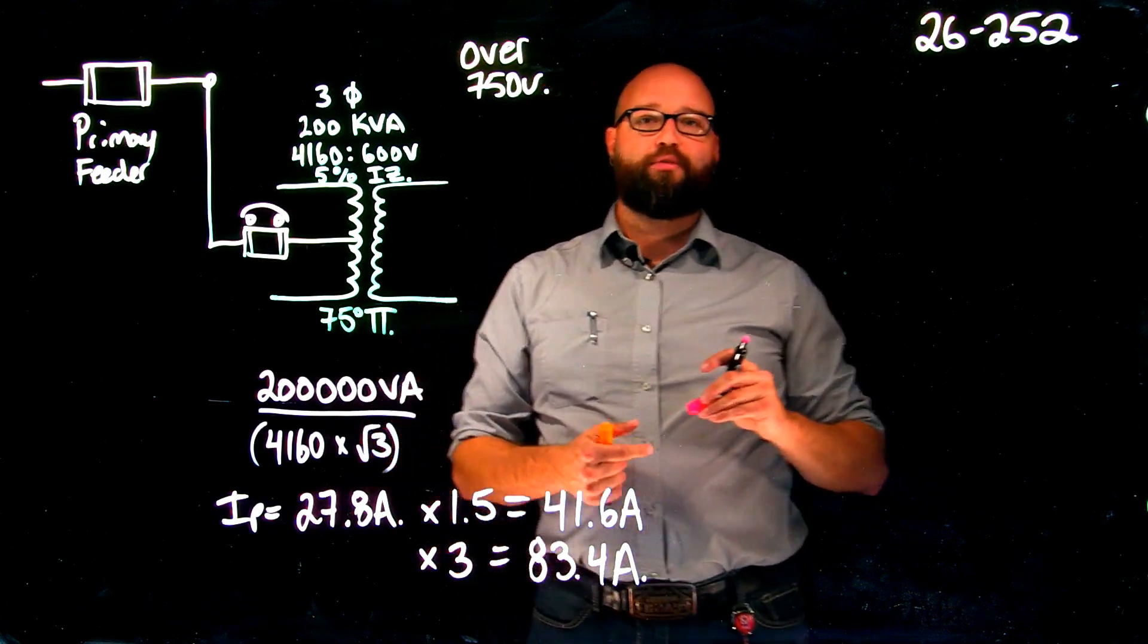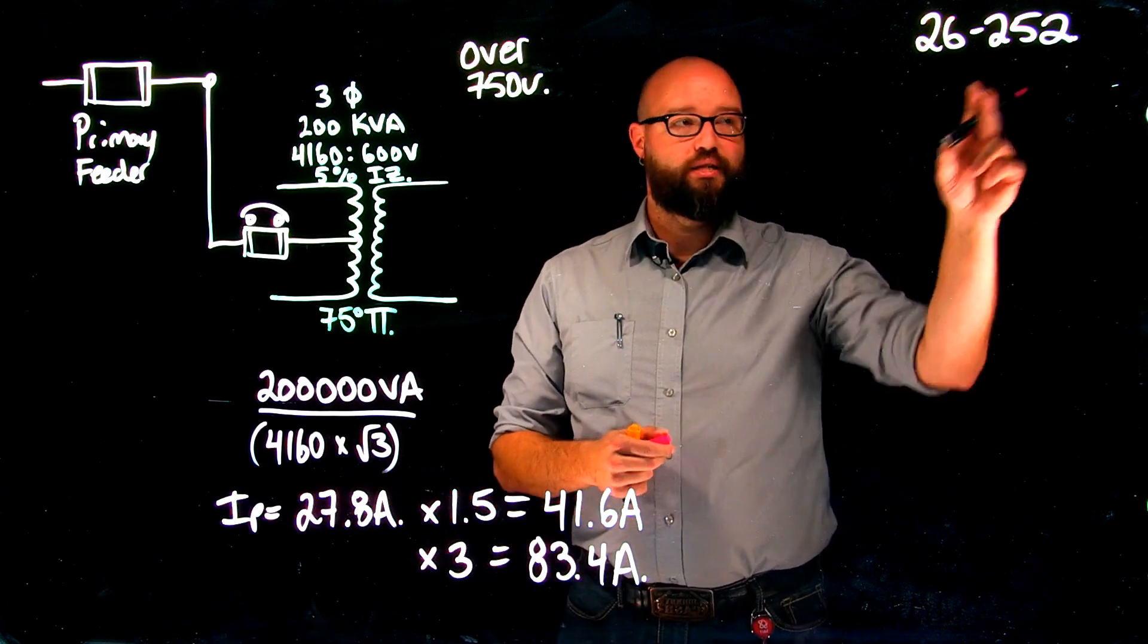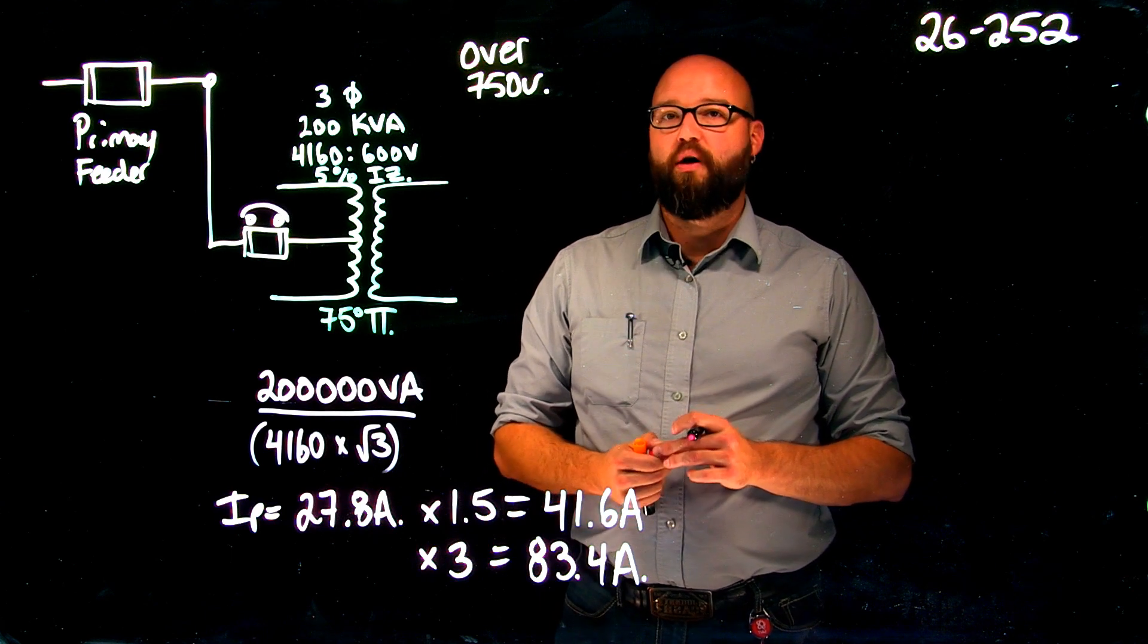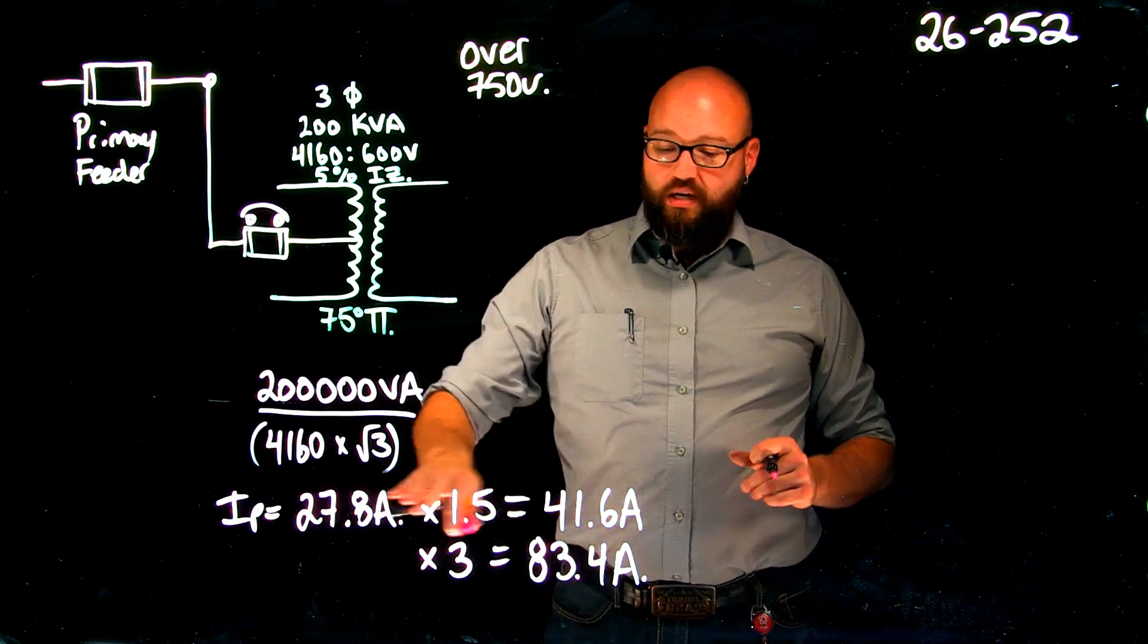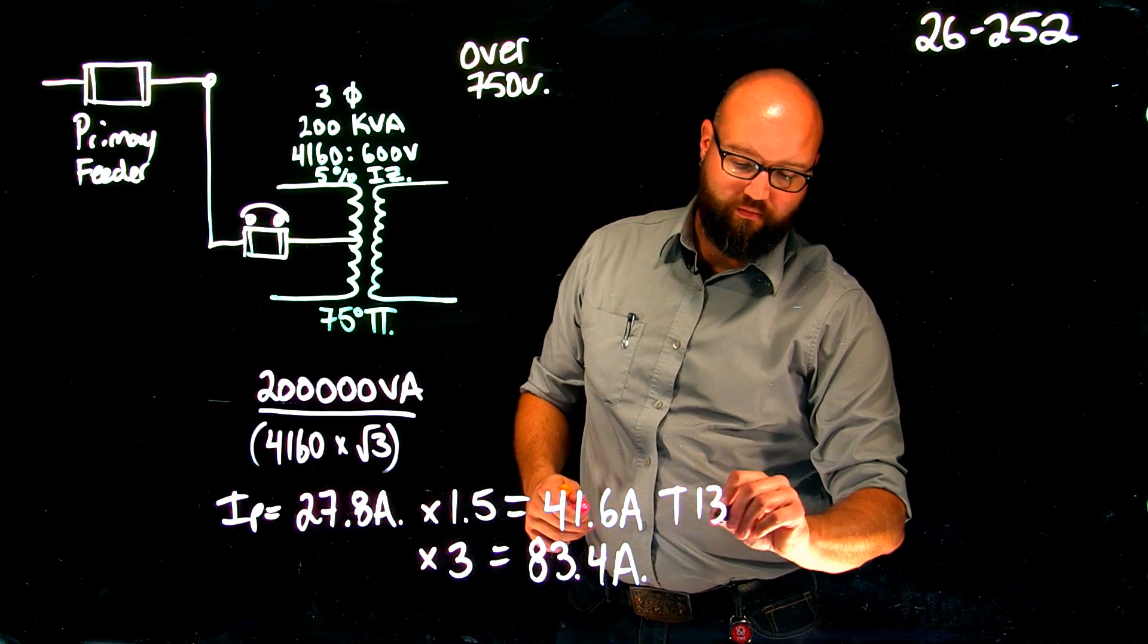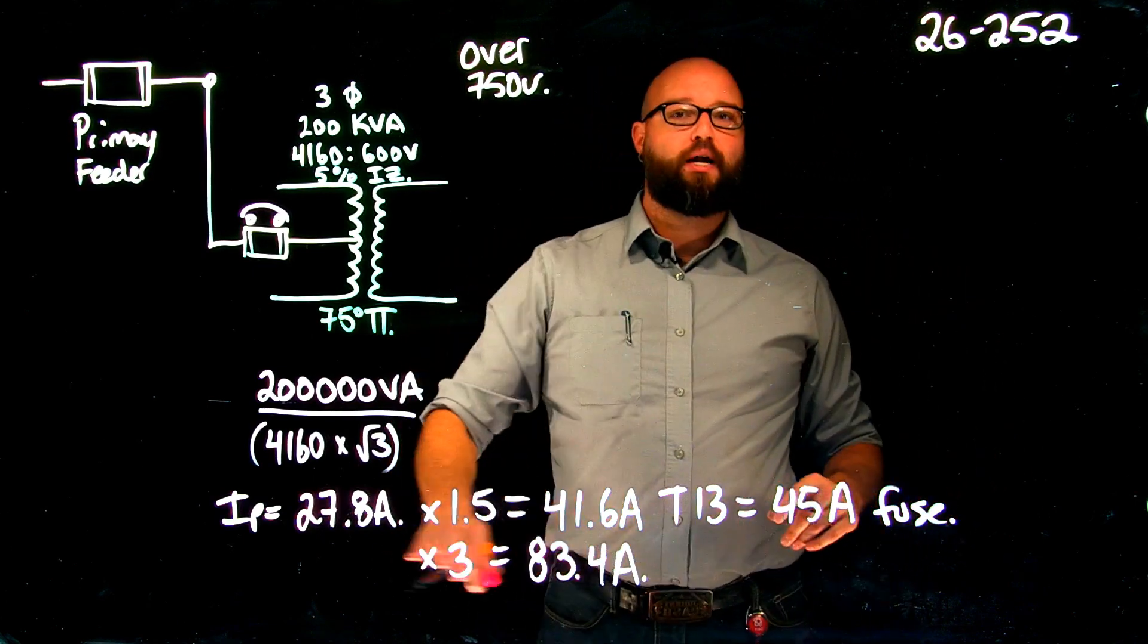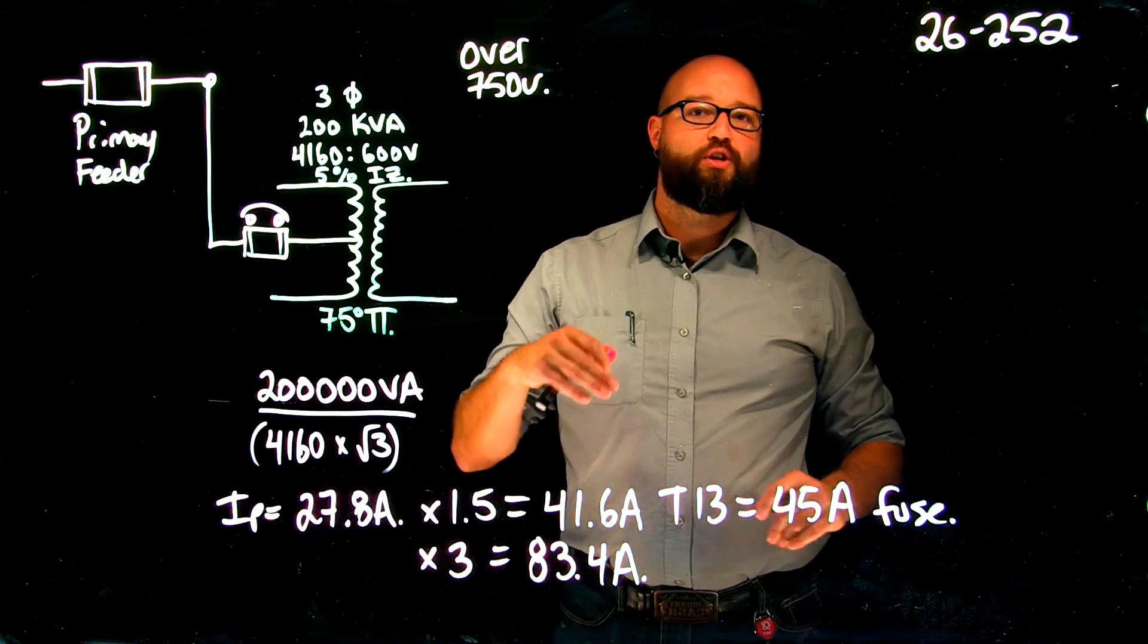This is where we would go to table 13 and select our overcurrent device. However, we need to continue reading on in 26-252 because there is an exception. It tells me that if 150% of rated current does not correspond to a standard fuse rating, we are allowed to go up to the next available size from table 13. So if I end up with 41.6, I'm allowed to go up to a 45 amp fuse, and that is specific to the fuse. There is no exception to the rule when it comes to the breaker.